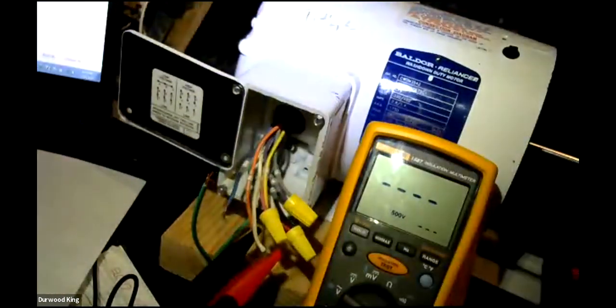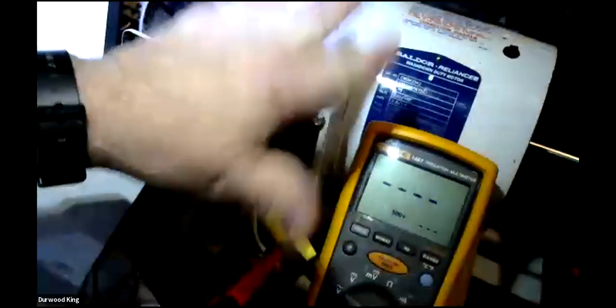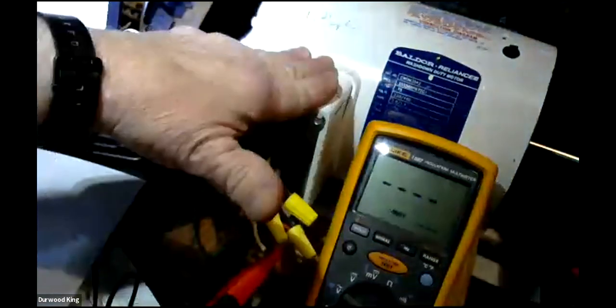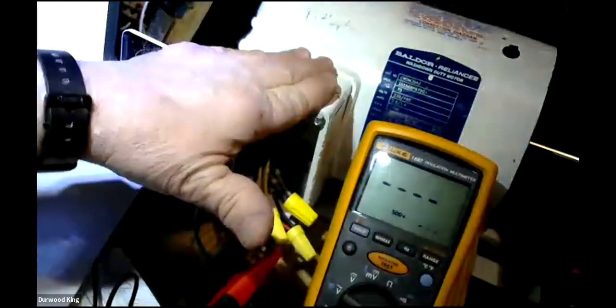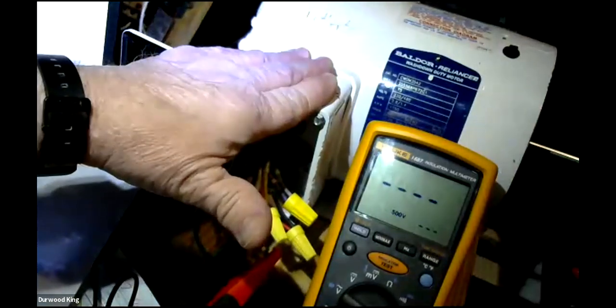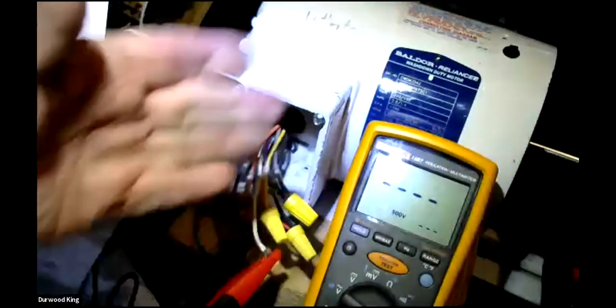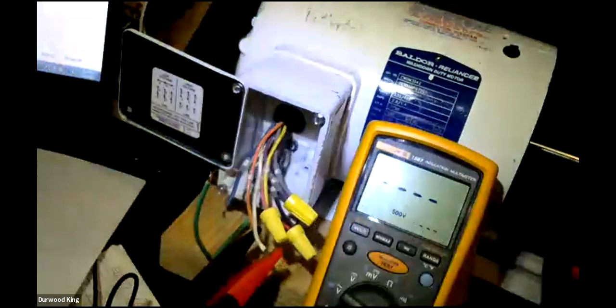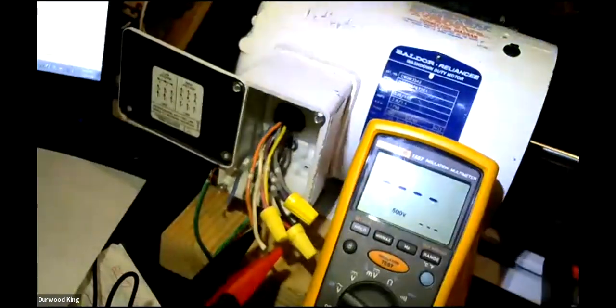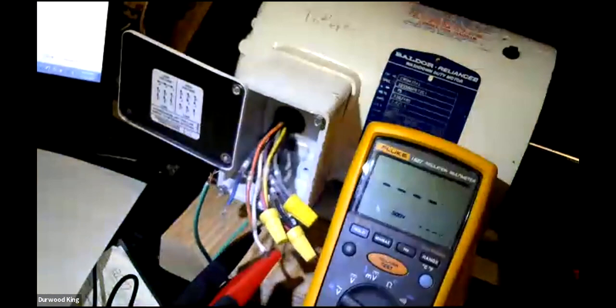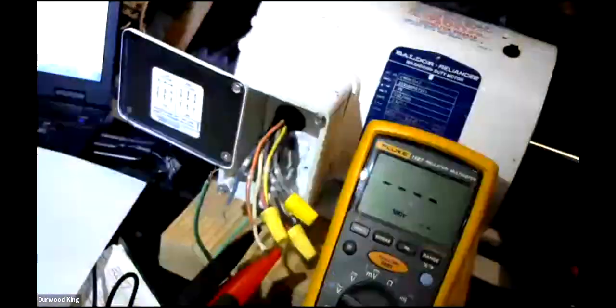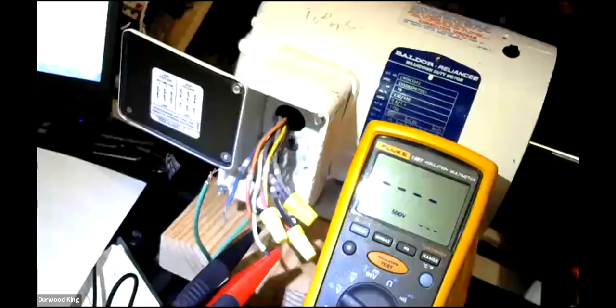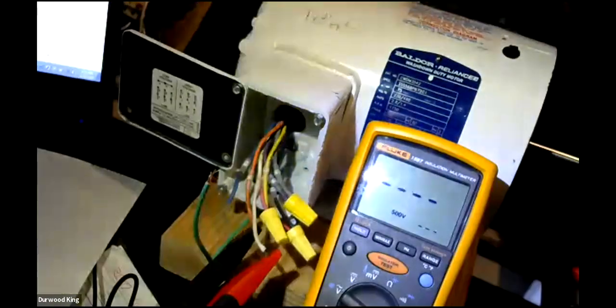The only thing I ever knew about checking on them was to check them to ground. But then I got to thinking, maybe I need to check through the motor, and I did that, and that's where it showed up. When you check resistance through the motor, that's where it showed up that it had an open leg. What do you think about that?